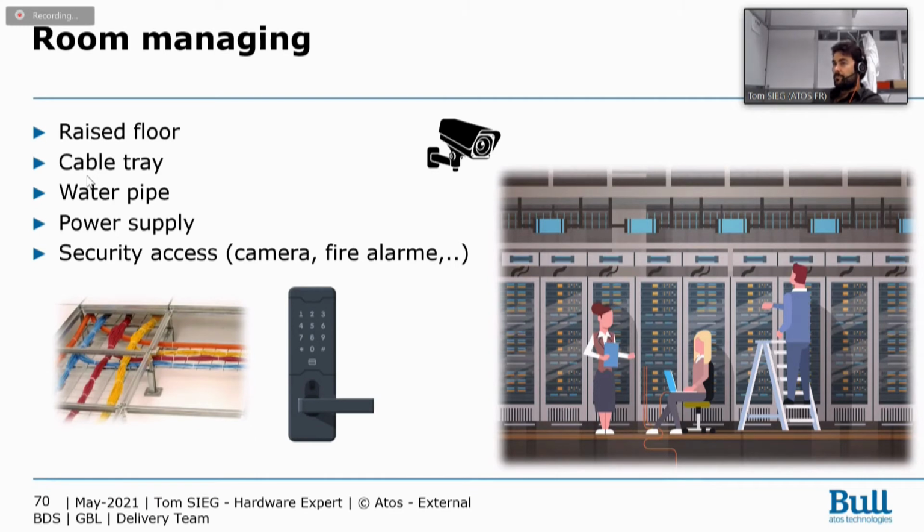The piping will be in the bottom part. You have piping, of course, if you have water coolers, if you have a direct cooling system, or when you have a heat exchanger directly in the data center room, which is the case for many data centers. So in those cases, a raised floor is always useful.